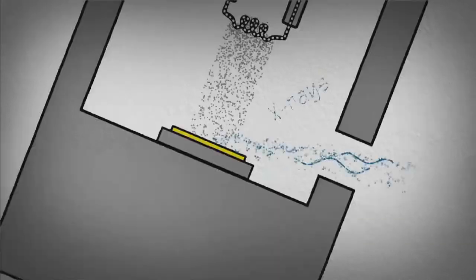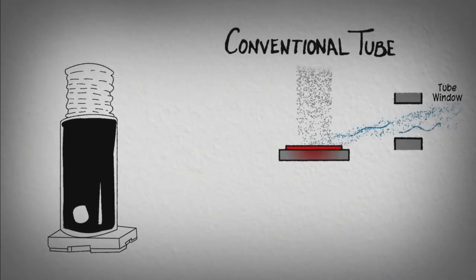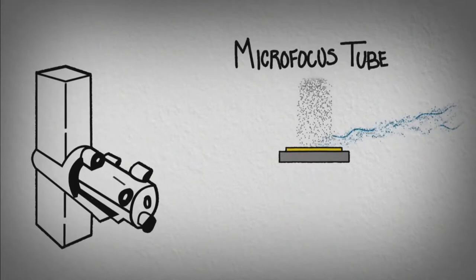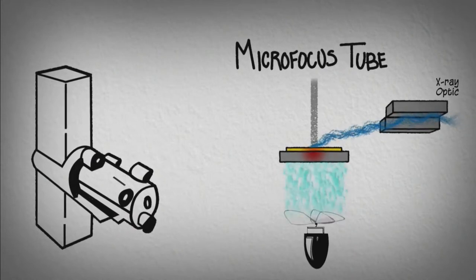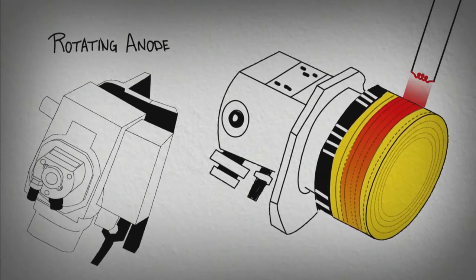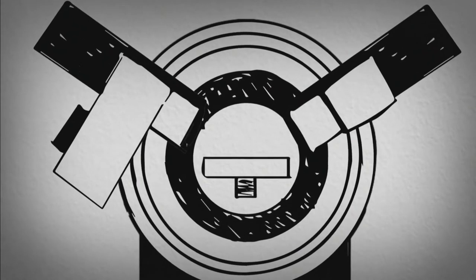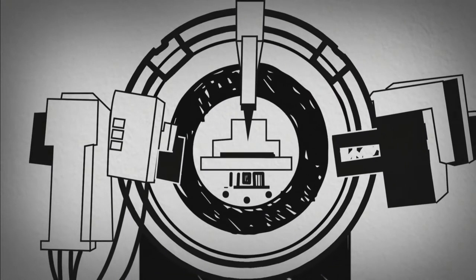In addition to creating x-rays, a large amount of energy is converted into heat, requiring the anode to be cooled. In the traditional tube, the large footprint of the wide electron beam limits heat dissipation, requiring water cooling. By using a small spot-shaped electron beam, heat can be dissipated in three dimensions — these microfocus sources allow the anode to be air-cooled and produce a very bright spot beam. If maximum signal is required, a rotating anode source is the best choice; the anode is spun at several thousand RPM, evenly distributing heat, allowing operation at much higher power.